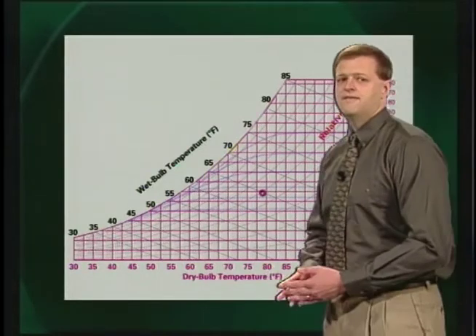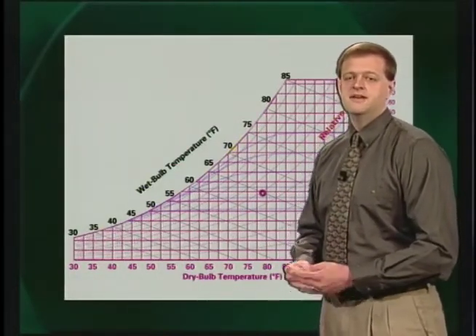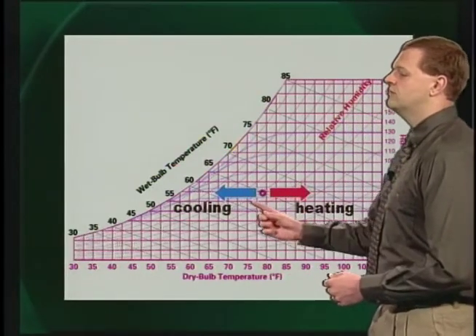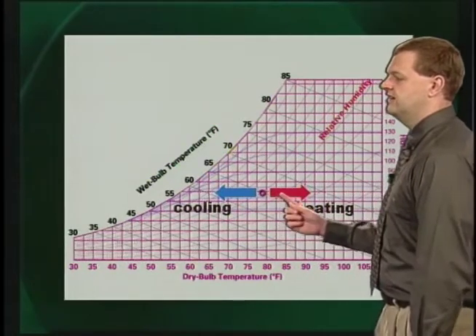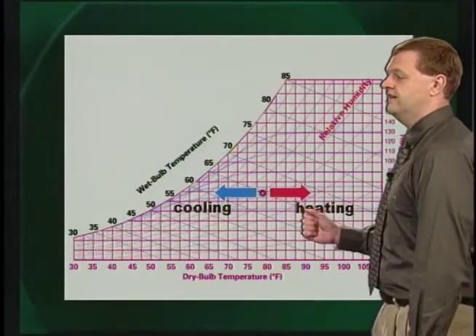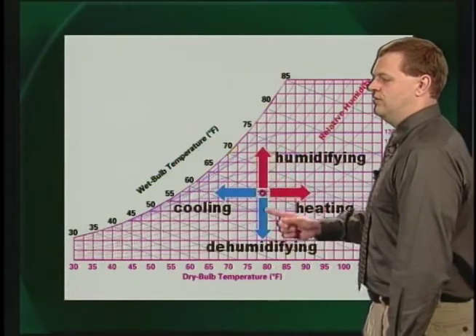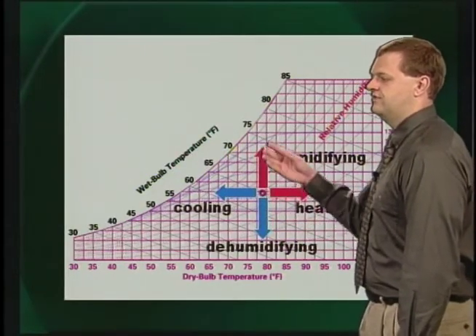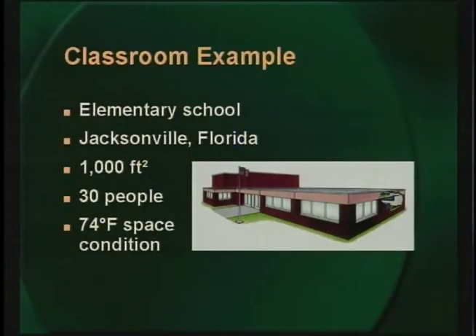The psychrometric chart is often used to graphically represent the basic processes that occur within an HVAC system. For example, if sensible heat is added or removed with no change of moisture content, the condition of the air moves horizontally on the chart. On the other hand, if moisture is added or removed without changing dry bulb temperature, the condition of the air moves vertically on the chart. Throughout this broadcast, we will consider an example classroom in an elementary school.